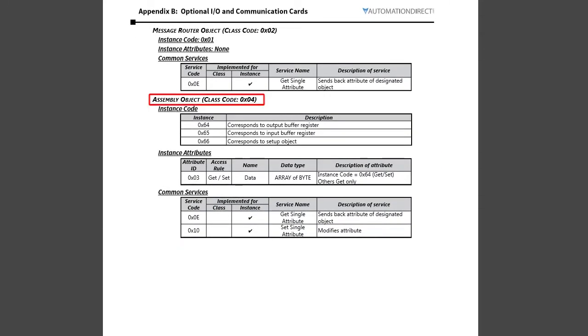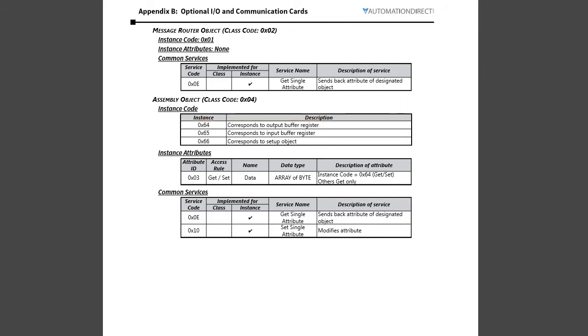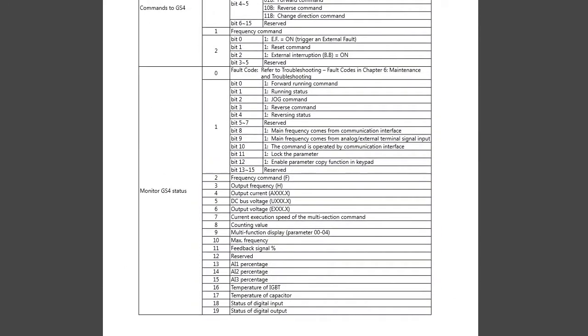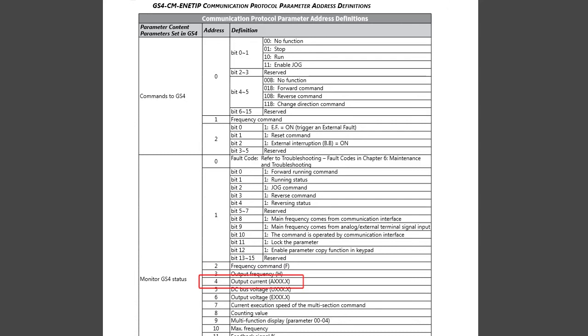Let's scroll down to the assembly class. Here is class number 4 and has three instances. We used instance 101 before which was the input buffer. That's the data into us which is out of the GS4 drive. Instance 100 is the output buffer which is the data out of us into the drive. Input and output in Ethernet IP is always relative to the originator which in our case is the PC that we are originating the messages from. How did I know earlier that bytes 10 and 11 of the input buffer were the DC bus voltage? That was back here in the buffer definition chart. Sure enough, the DC bus voltage is word 5 which is bytes 10 and 11. We can view any of these attributes – drive frequency, output current, run status, etc.